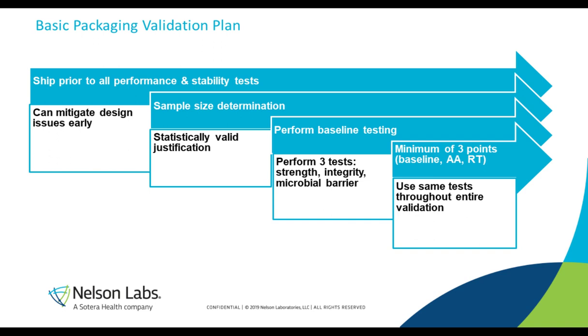We do, after our ship testing, we look at baseline testing and we perform 3 tests. We evaluate strength, integrity, and microbial barrier as outlined by the standard. And I'm going to go through one of these tests in depth as we go through this webinar. The important part is that you're going to look at a minimum of 3 points. You're going to do baseline, which will determine whether there were any issues for your samples after ship testing.